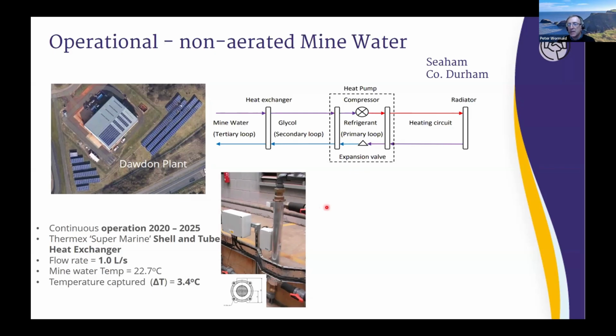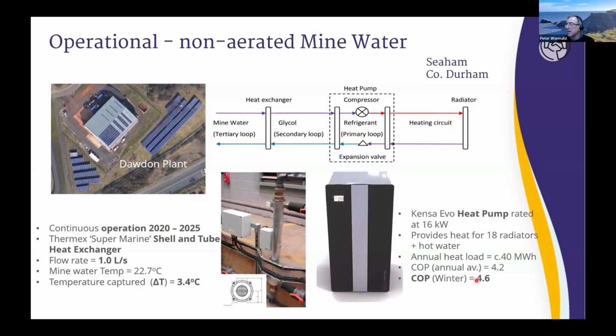flushing requirements. It uses a Thermex shell and tube heat exchanger, accessing a flow rate of mine water of 1 litre per second. Mine water temperature is approximately 23 degrees, and the temperature captured, or delta T, is about 3.5 degrees. There's one heat pump rated at 16 kilowatts, and that provides heat for 18 radiators and hot water. And there's a COP, or coefficient of performance, very healthy one. In winter 4.6, and the annual average is 4.2.